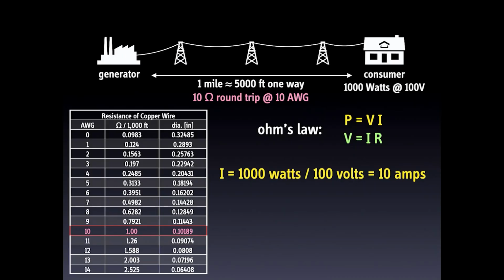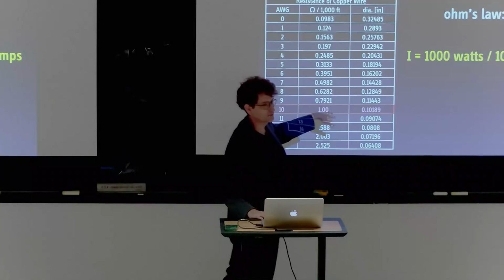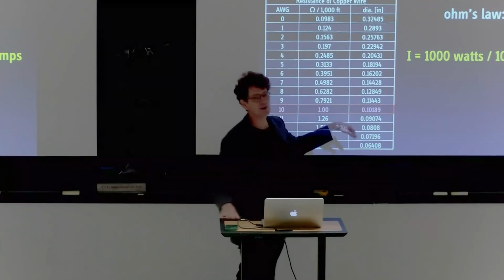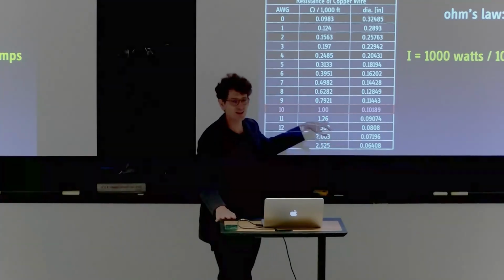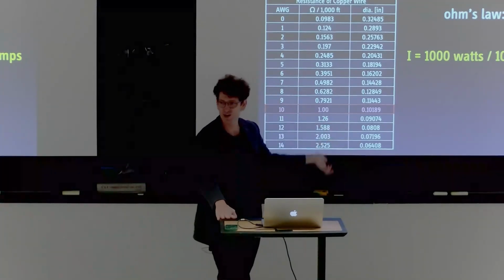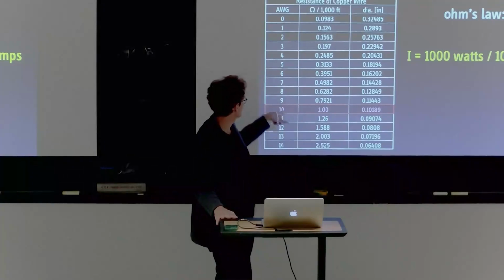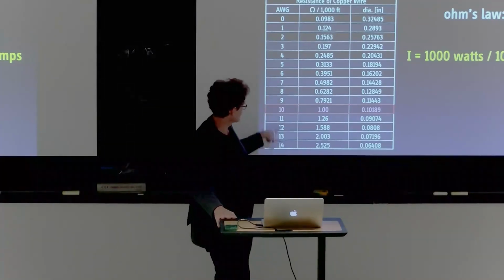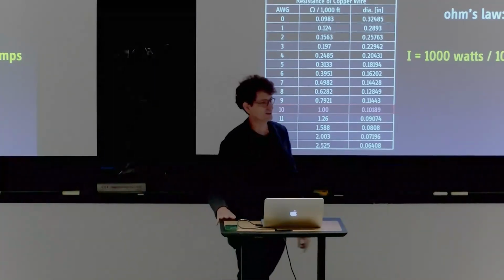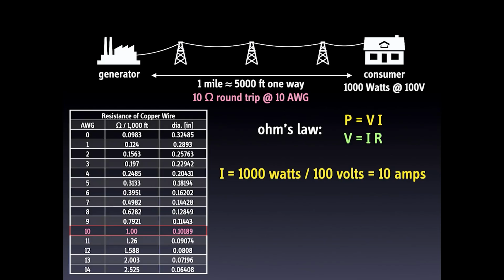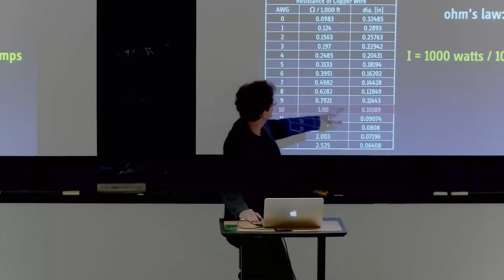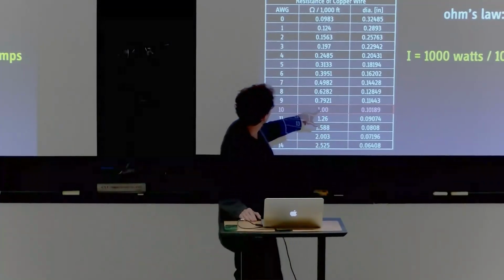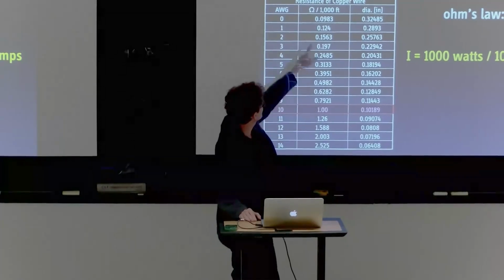If you look up the resistance of copper wire, this is 10 AWG, American wire gauge. I don't know if you know your wire gauges, but this is a little fatter than what you have in your house, which is typically 14 for 15 amp service or 12 for 20 amp service. This is not a shoddy thin wire, and it has a loss of 1 ohm per 1,000 feet.